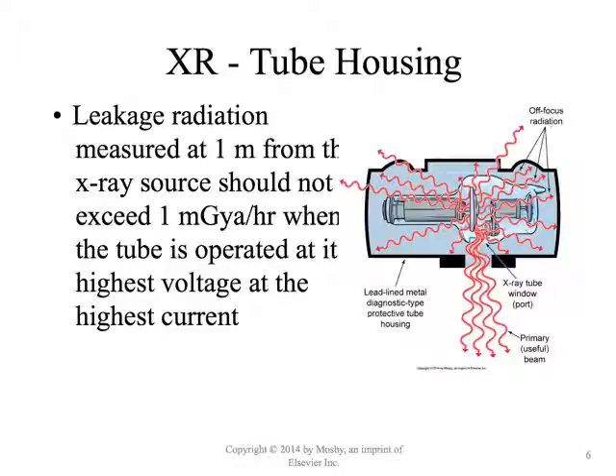For X-ray, now let's get down into the various modalities that we're practicing in and talk about specifically. Leakage radiation from the X-ray tube. If we measure it 1 meter away from that tube, it should not exceed 1 milligray in air per hour. So measured 1 meter from the tube, it should not exceed 1 milligray, right? And that's when it's operating at the highest tube voltage that could be operated at continuously.